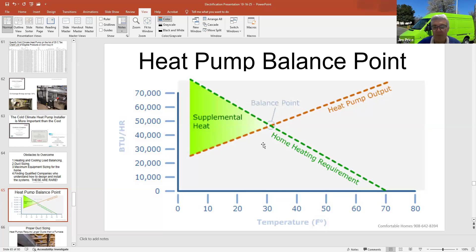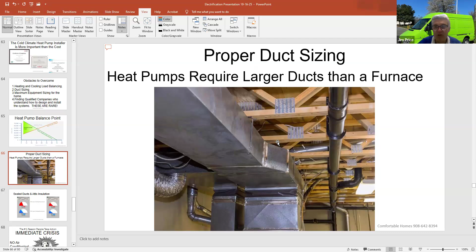Proper duct sizing is critical when you take out the furnace and put in a heat pump. So anybody who's not addressing your ductwork, and especially your return air, throw them right out of your house. Don't even listen to them, because they're going to screw it up. You're never going to be happy, and they're not going to get it right. The worst thing you could do is not address that issue.